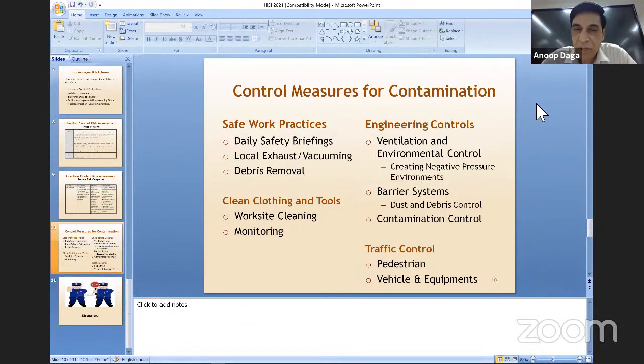Now, when we plan for an immunocompromised patient versus a patient who is bound to give infection to us, like a tuberculosis patient, we call it the concept of positive pressure and negative pressure. That's an altogether different topic for discussion. Positive pressure means we need to have positive pressure inside the room. Like Dr. Harshvardhan told rightly, we need to have a minimum of 4 air changes per hour, 4 air changes of fresh air per hour into that room, almost like an operation theater area.